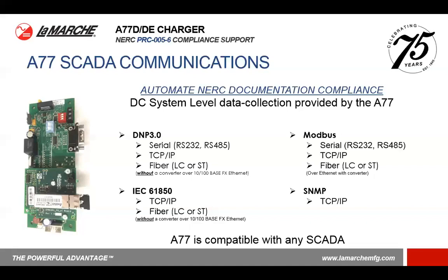Something that's very important about this is because you're using it at a BES site, it's important to have NERC cybersecurity in mind. We've actually put the A77 through a third-party NERC CIP cyber penetration test and passed with flying colors, allowing us to be spec'd into systems that are on the BES.